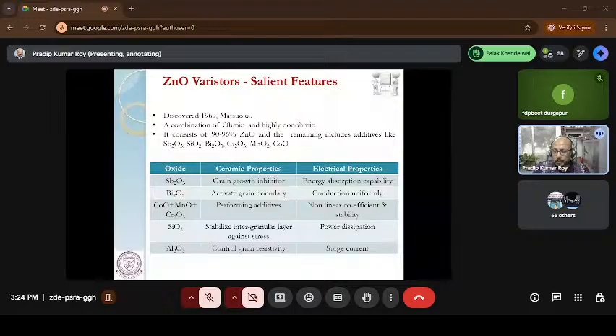Antimony oxide is mostly used as a grain growth inhibitor. Grain growth inhibitor means you have to control the grain size during the operation, and in the electrical aspect, it increases the energy handling capability. All the transition oxides like cobalt, manganese and chromium increase the non-linear performance of the surge arrestor. Non-linear means a small change in voltage causes a huge amount of current to pass through the surge arrestor. And the remaining two, silicon and alumina, are somewhat responsible for the loss parameter, which is very essential, normally what we call the watt loss. These two oxides are very much responsible for that. So this is basically the multi-oxide system used to manufacture the varistor.